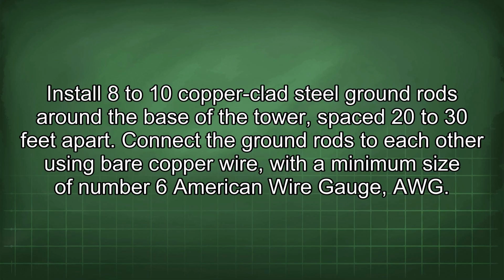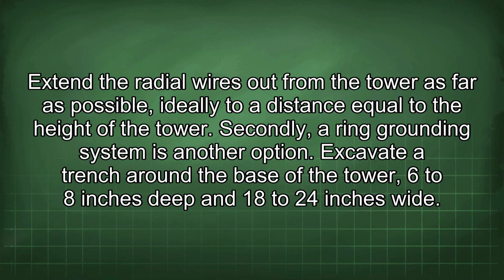Connect the ground rods to each other using bare copper wire, with a minimum size of number 6 American wire gauge, AWG. Extend the radial wires out from the tower as far as possible, ideally to a distance equal to the height of the tower.